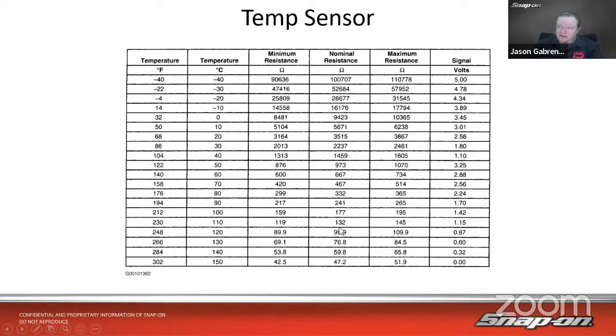And you'll see the resistance does go down. I start at 100,000 nominal all the way down to 47 ohms nominal. So that's a pretty good swing. If you're testing resistance, it's not really going to trip you up. What's going to trip you up is the voltage. If I'm testing voltage on that, and we'll see if it gets to 104 degrees Fahrenheit, I'm at 1.10 volts. If I go to 122 degrees Fahrenheit, 18 degrees more, I'm back to 3.25 volts.